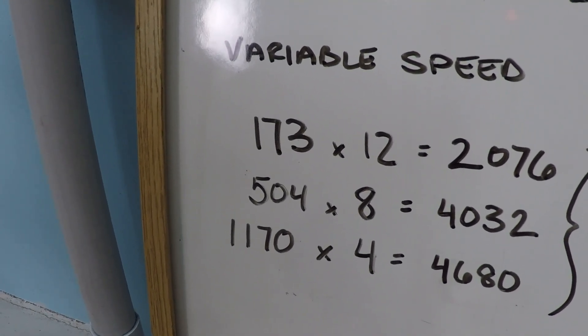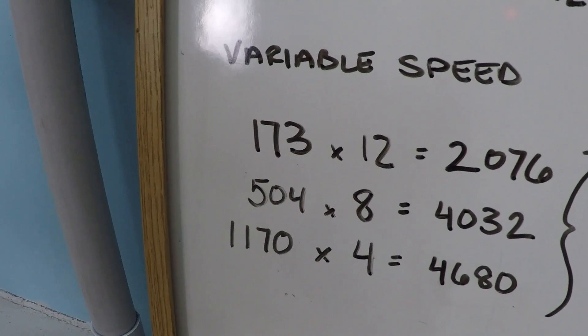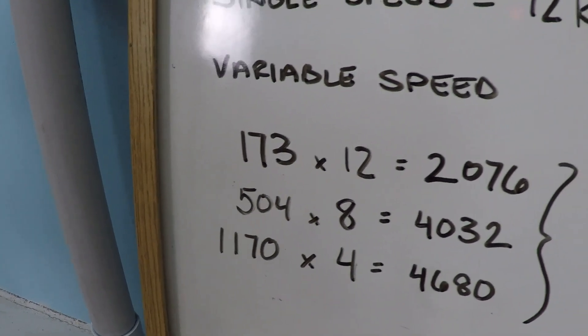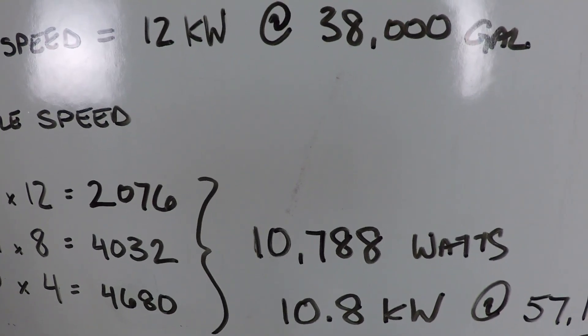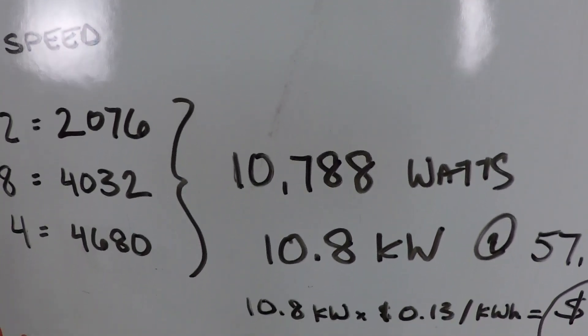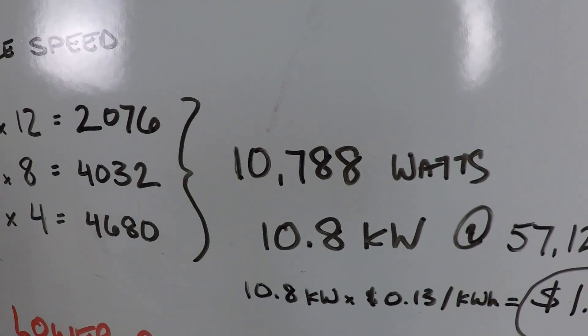173 watts at 12 hours, 504 watts at 8 hours, 1170 watts at 4 hours, subtotals. That is your total power consumption, 10,788 watts, which rounds up to 10.8 kilowatts.